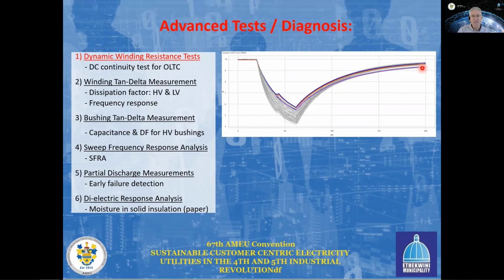This process takes roughly about 200 milliseconds going through. But the transition, or this fingerprint from one tap to the next, is identical, or should be the same or similar for all the tap transitions, both tapping up, tapping down, as well as for the different phases. So all those transitions in a tap changer, and in this case here for a 17 tap power transformer, this is actually 96 different transitions, should all basically be able to fit on top of each other.